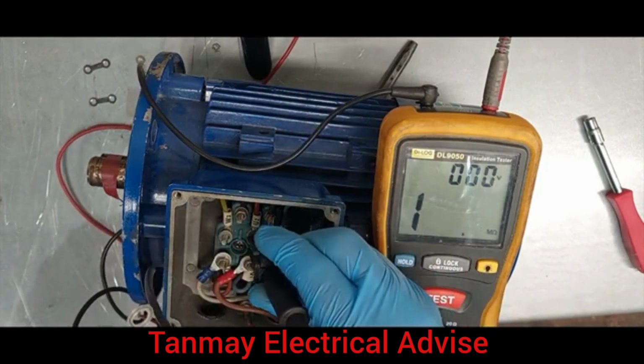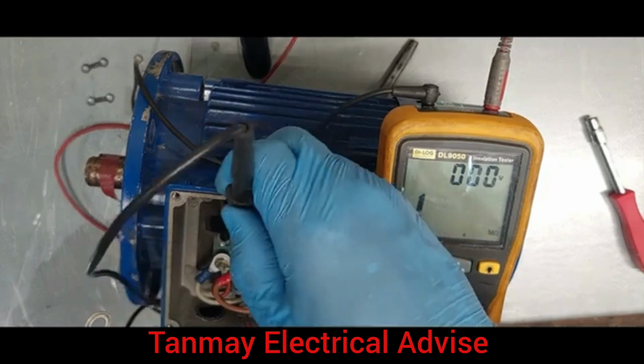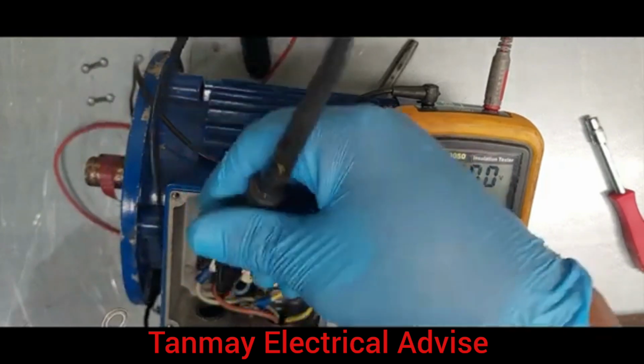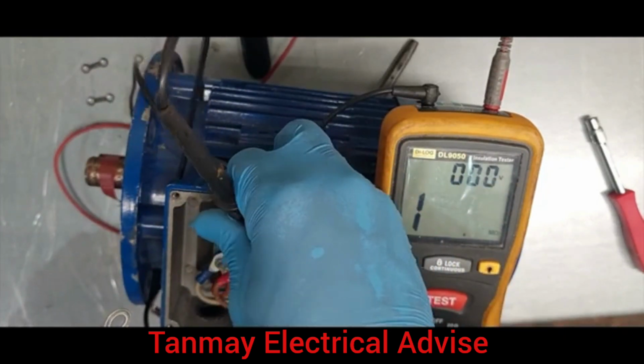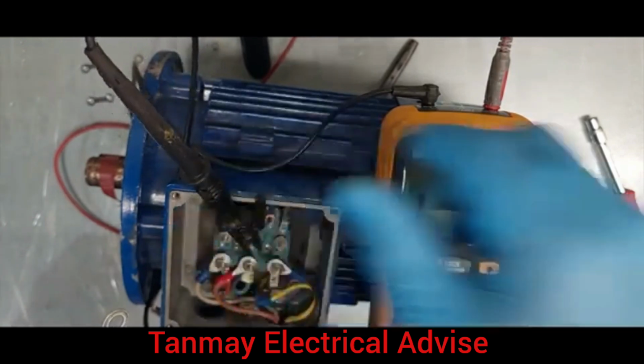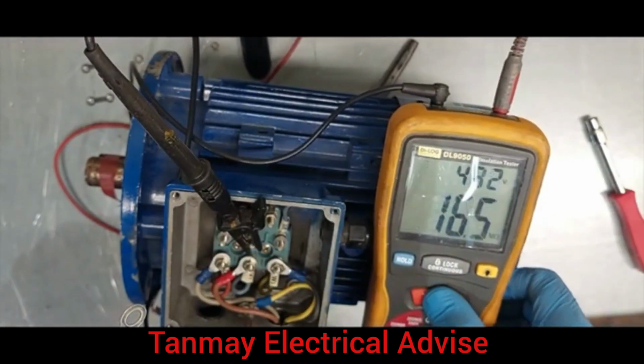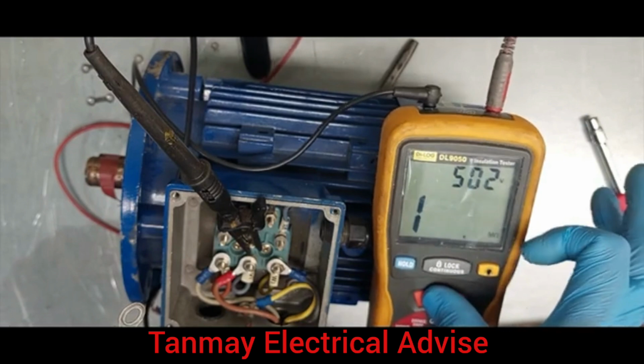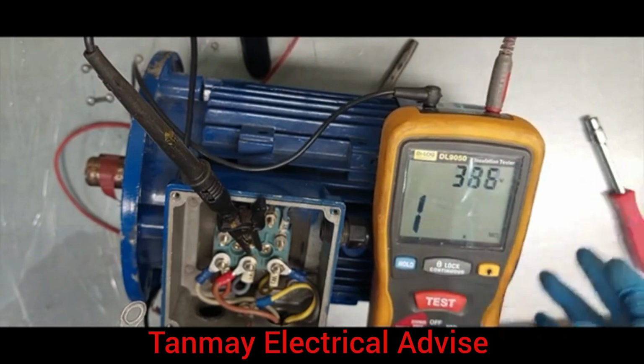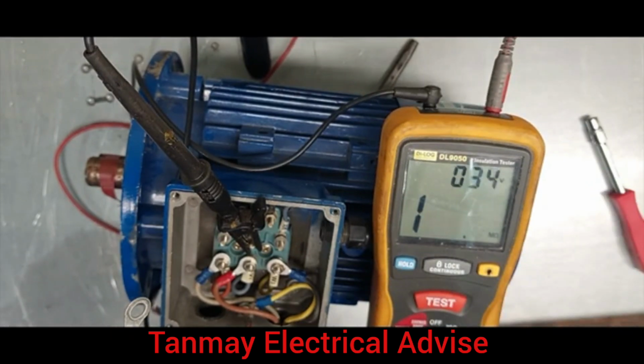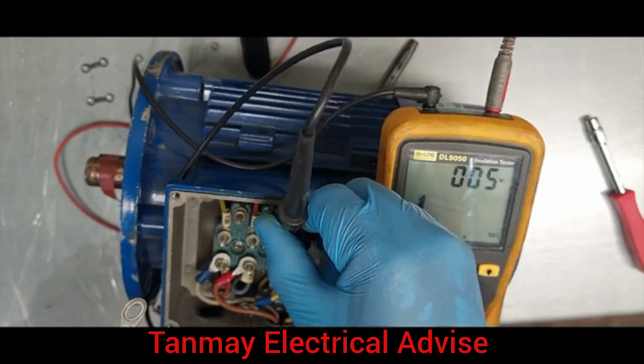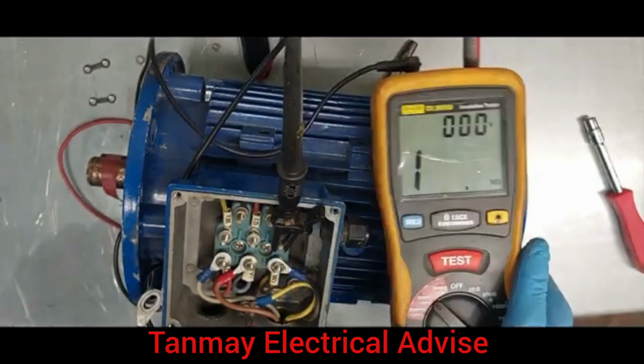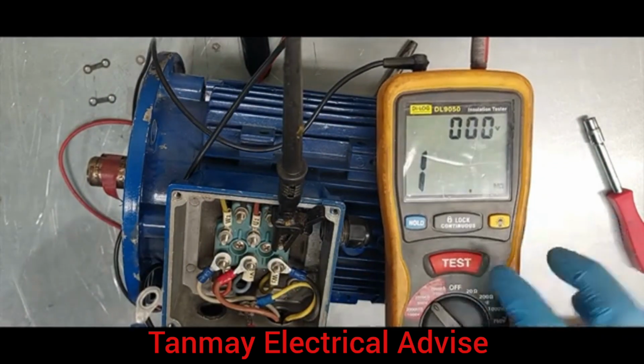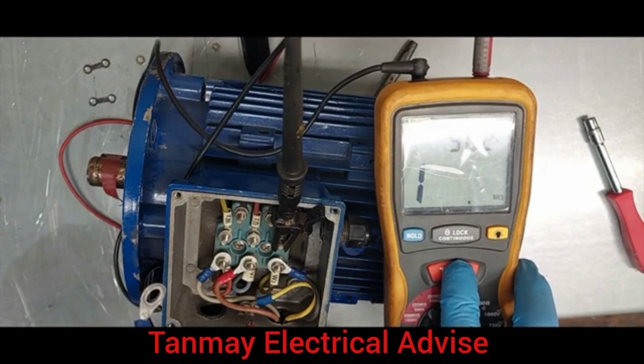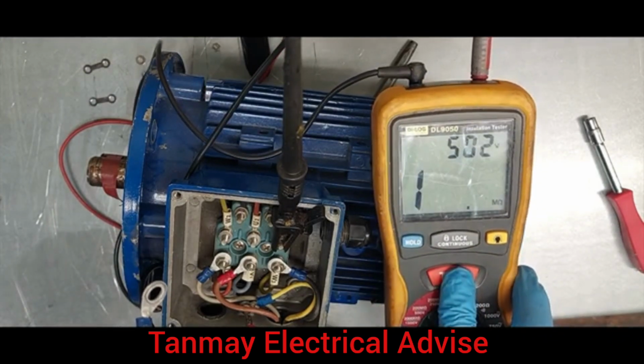We do the same for U. Between U2 and chassis, we inject 500 volts, and we have 1 mega ohm return. We check V2. We inject 500 volts, and we have 1 mega ohm returns.